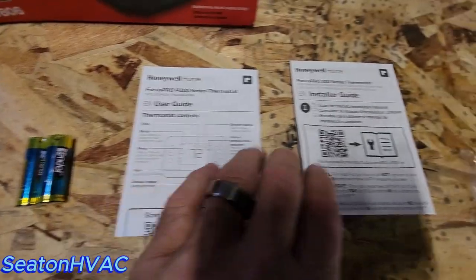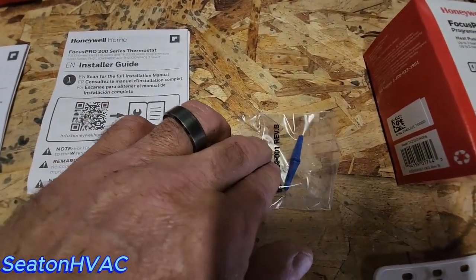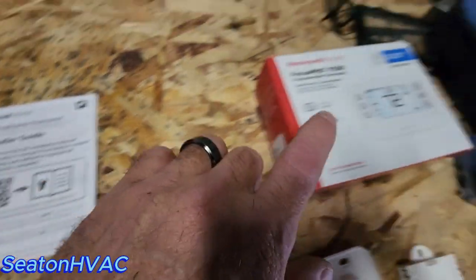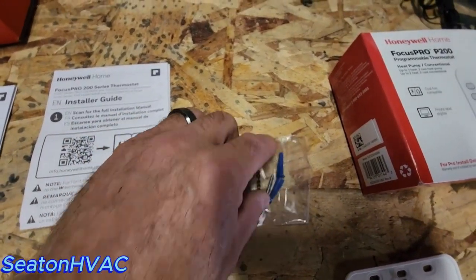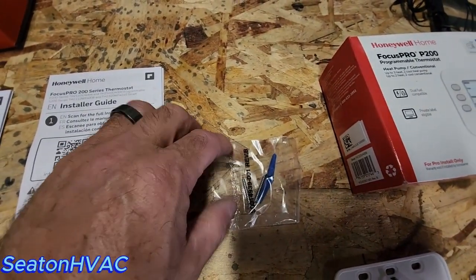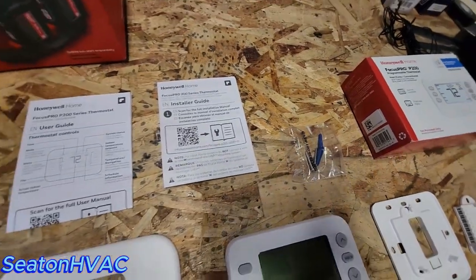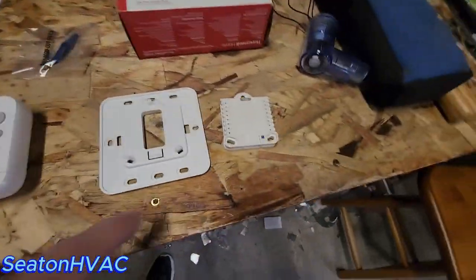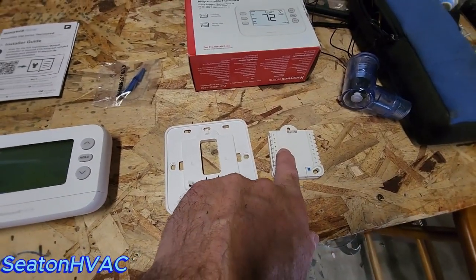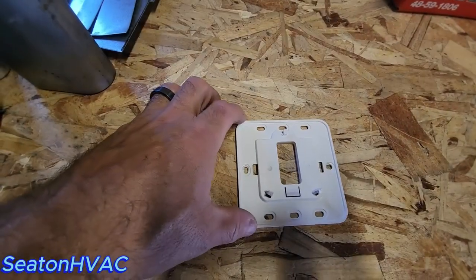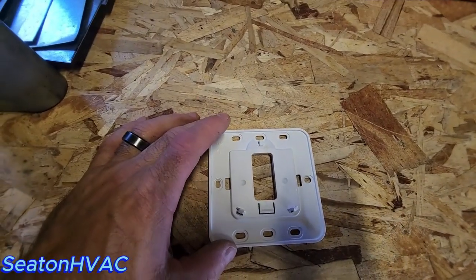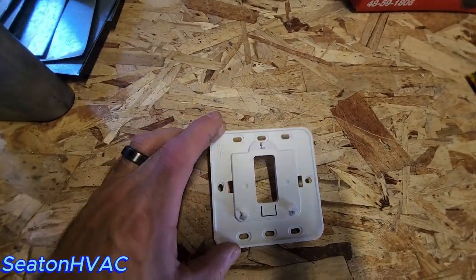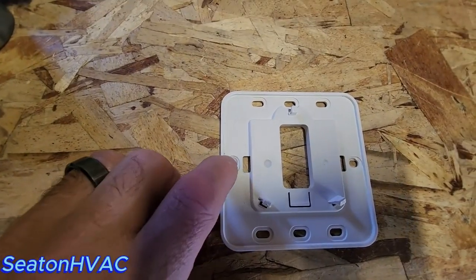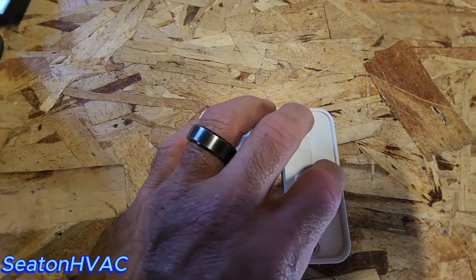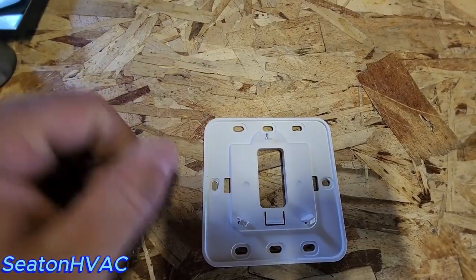It comes with a user guide, installer guide, and some wall anchors and screws. These actually aren't the ones that I actually stole out of this, but it comes with actually 3 heavier duty anchors and 3 screws, but it'll always have those in there. So what do we want to go over first? Let's go over the terminals on this guy and how all this goes together. Okay, typically the first thing you're going to do on these before you do anything else is you're going to mount this guy on the wall. You're going to mark, make sure it's level on the wall. You're going to mark there, and either top or bottom because it gives you 3 anchors. Mark that, pull this off.